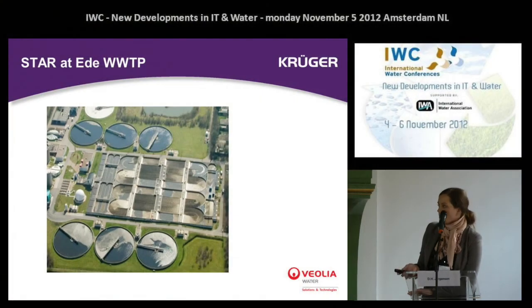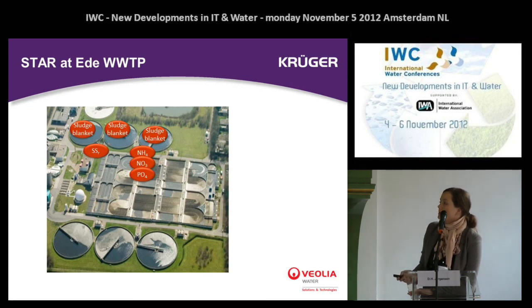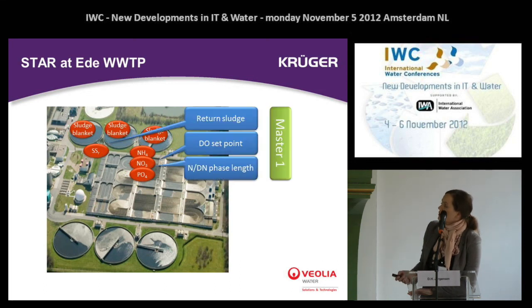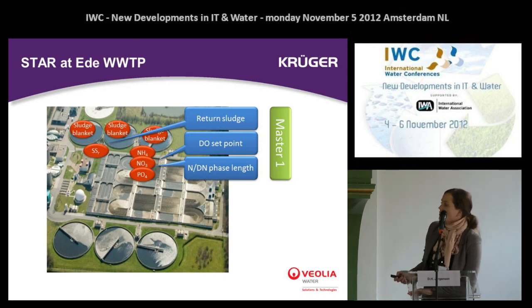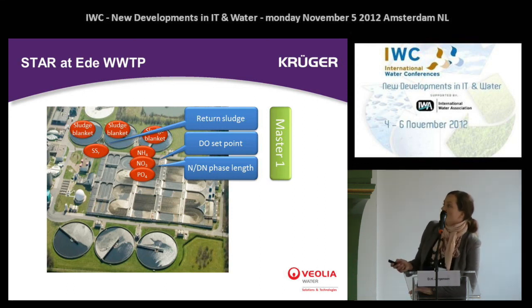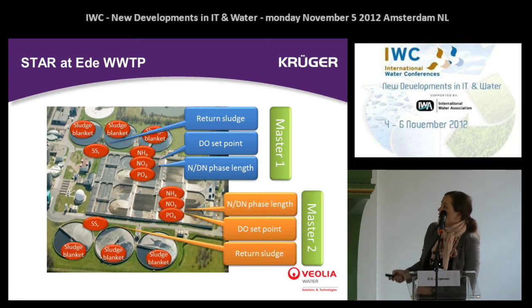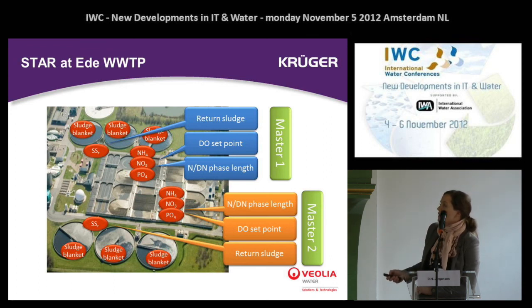Here is a photo of Ede Wastewater Treatment Plant showing the relevant and most important online meters. The picture shows which online meters are used for which control. For example, ammonia, nitrate, and phosphate are used for both the dissolved oxygen set point control and the NDN phase length control. For return sludge control, suspended solids and sludge blanket meters are used. STAR at Ede is set up as two individual masters, using the online sensors of each line for each master line control, meaning they can be controlled separately.